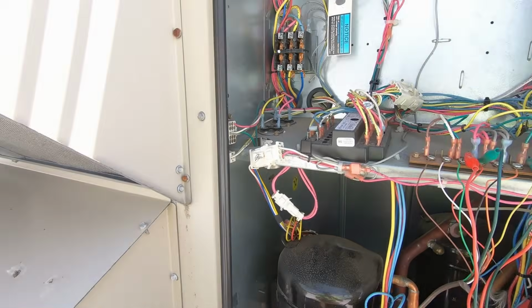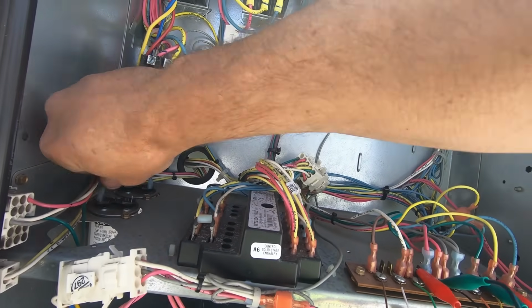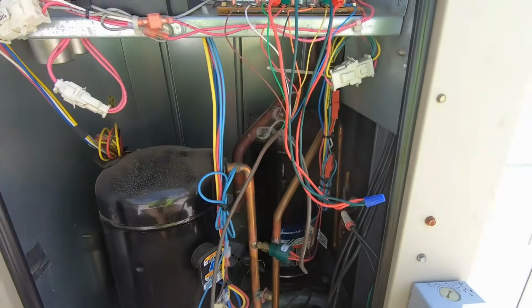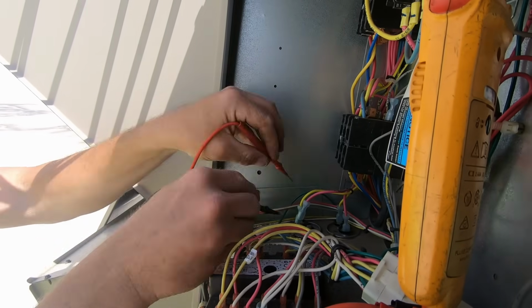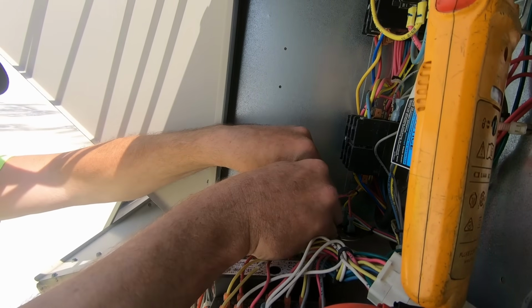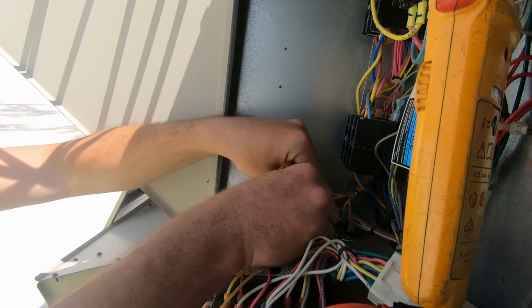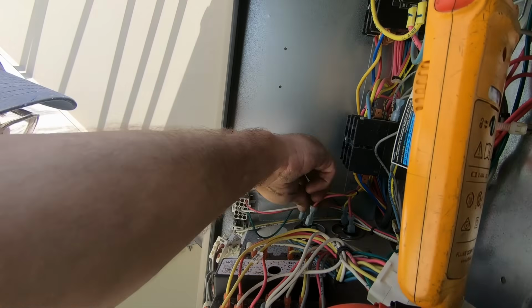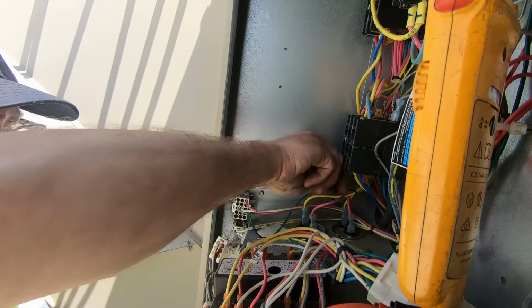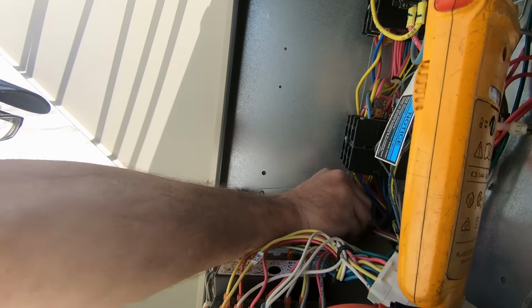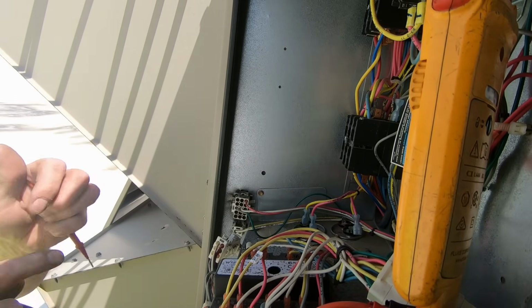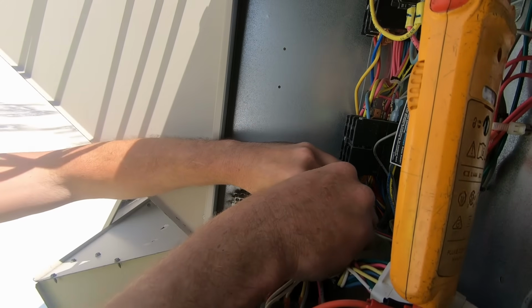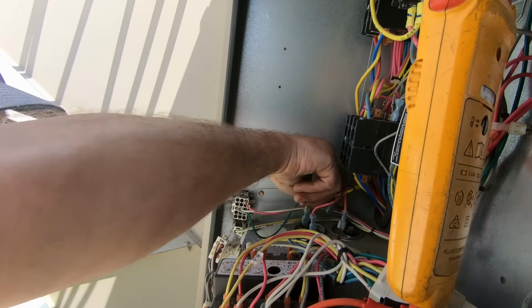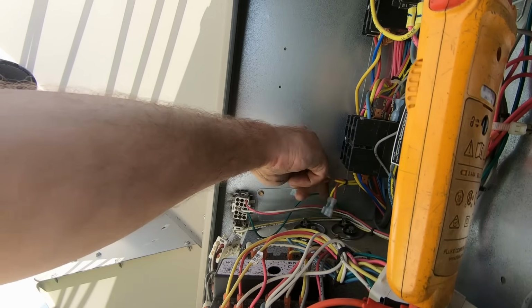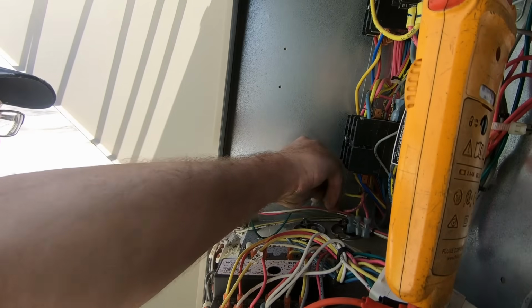Let's check these capacitors. 15 UF. Yeah. I think that's the one for our one that's not running. 11.5. That's weak. That is weak. Let's test this one. 14.4. I'm gonna swap these. See if that fan comes on.